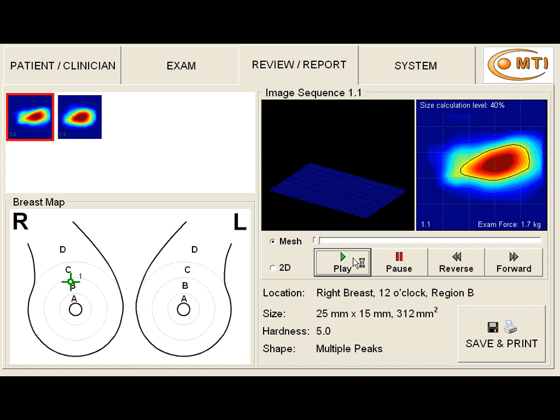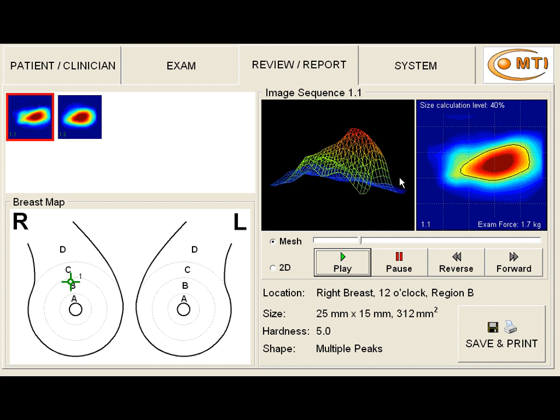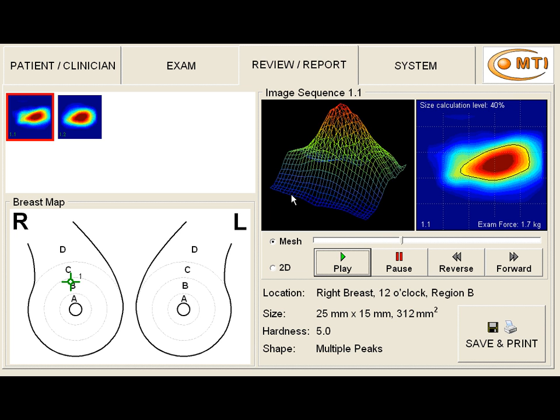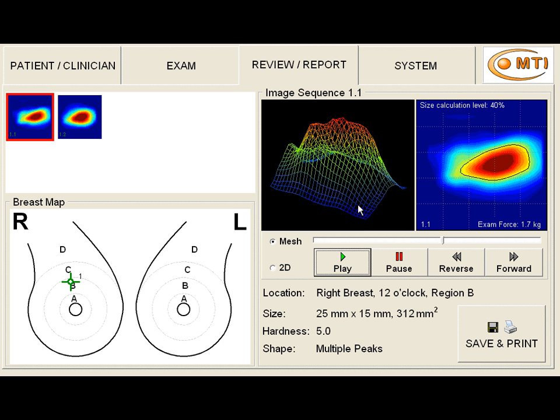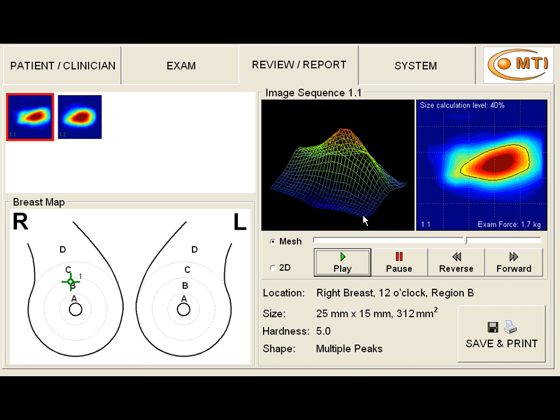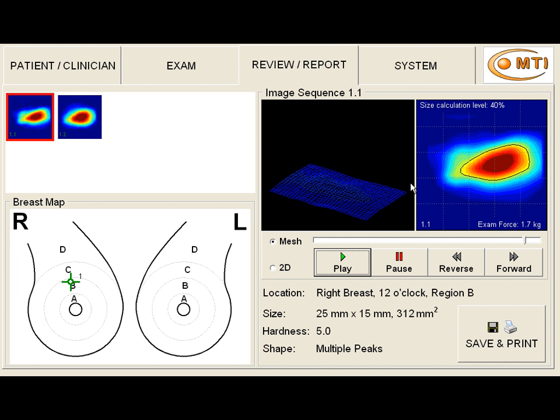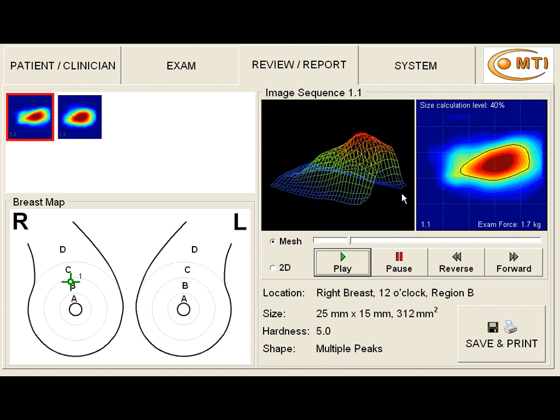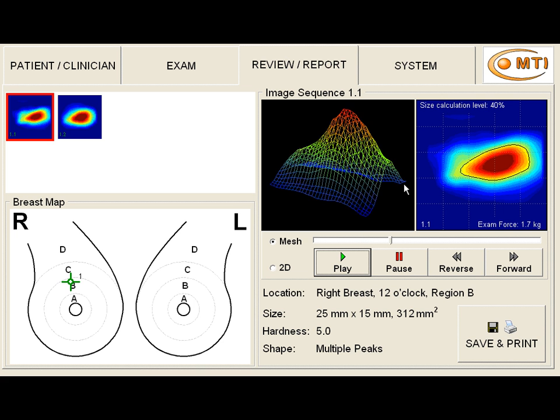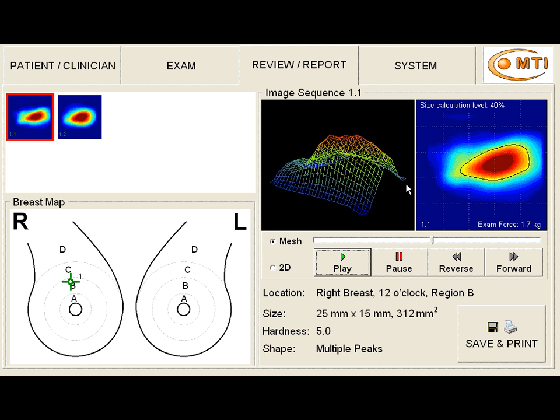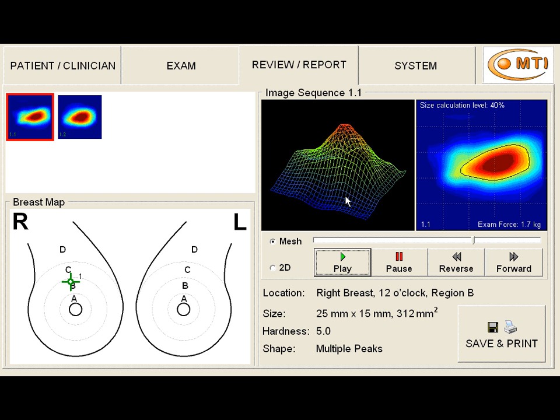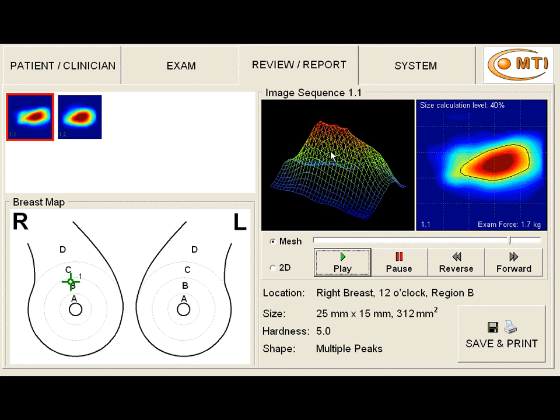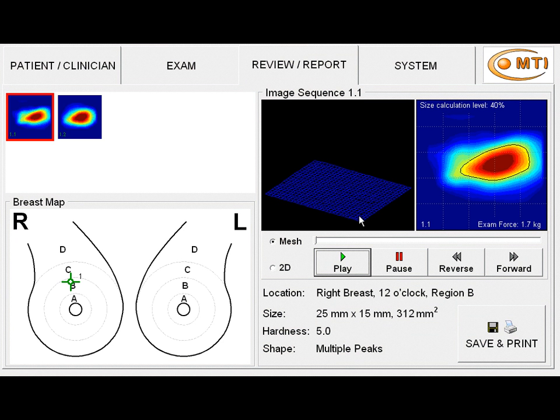The other thing that is useful for us to realize is that if the mass is much bigger than this, then it's going to encompass the entire transducer, and there won't be, like down here in the dark blue, the only normal breast tissue we can compare it to. But at least there is dark blue, these 3 points, these 3 corners, 1, 2, 3, watch it again, these 3 points, 1, 2, 3, and 4, are staying down at the baseline level. That one went up a little bit there. And that's the only way that the SureTouch can tell how tall this peak is, because there's some normal pressure here.